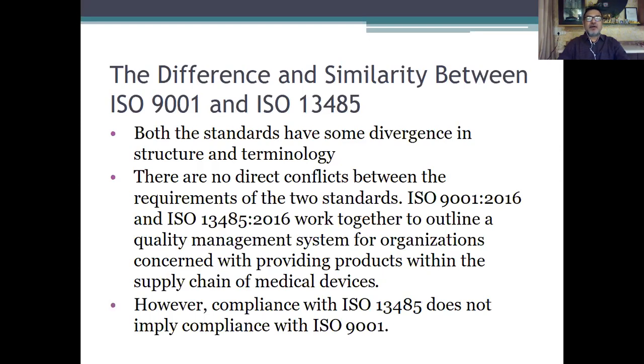ISO 13485 has an additional set of requirements specific to the medical device industry, and it discards some of the requirements of ISO 9001. Therefore, compliance with ISO 13485 does not imply compliance with ISO 9001, and any organization that aims to be compliant with both standards has to implement all applicable requirements of both ISO 9001 and ISO 13485.